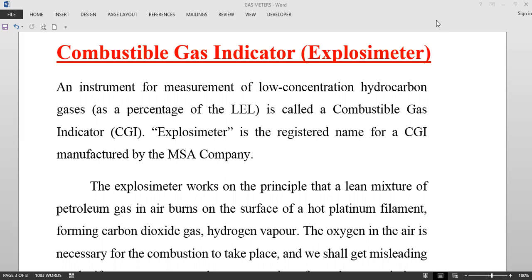One thing must be very clear: this equipment is to be used in a non-inert condition. Why? Because inside this equipment there is a minute explosion — or rather a mixture of gas burns inside this equipment. With that burning, it identifies or detects the presence of a gas. If it is an inert condition, there will not be any oxygen present, and for burning and fire we need oxygen, so it cannot be used in an inert condition.